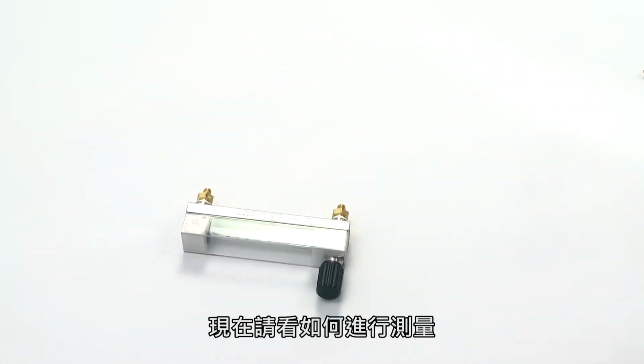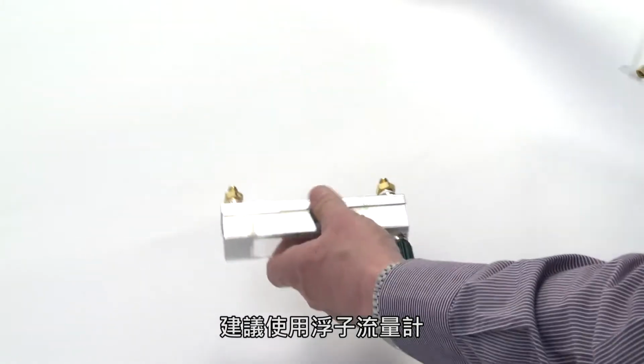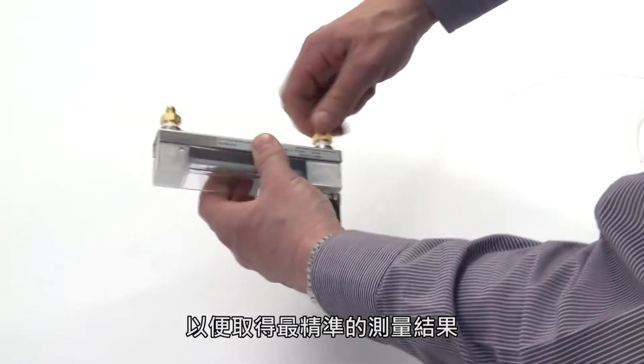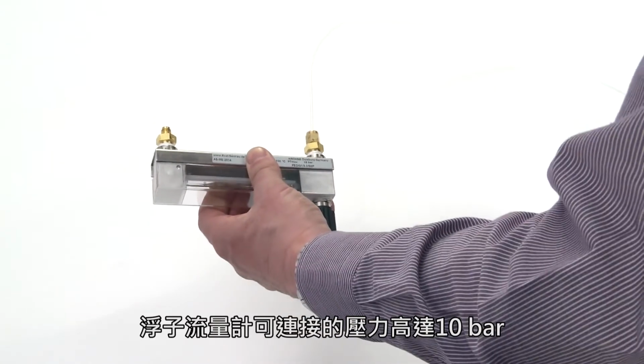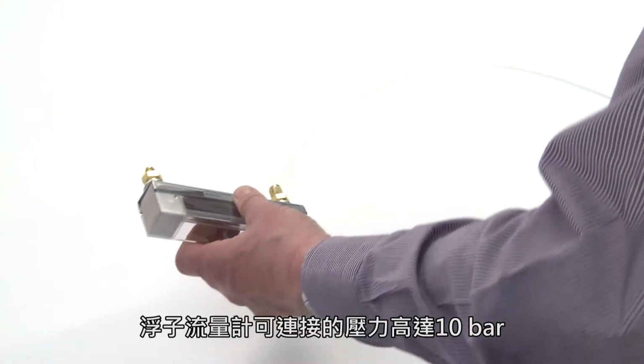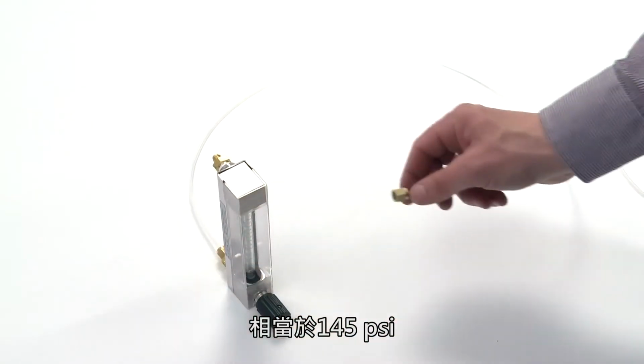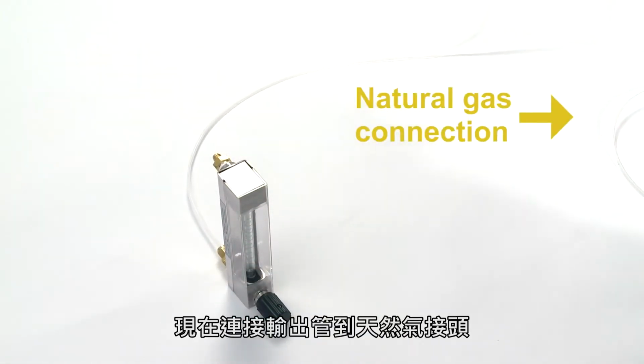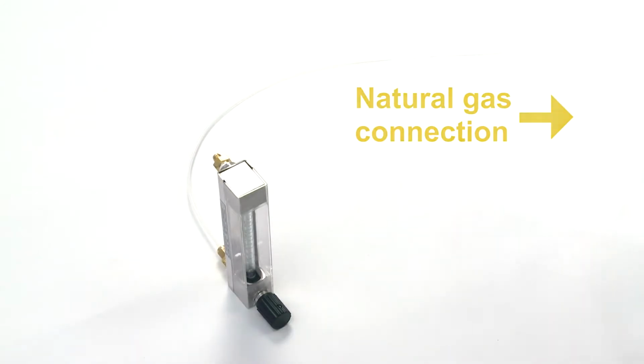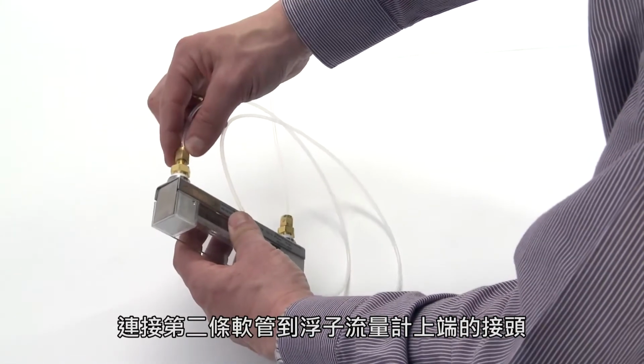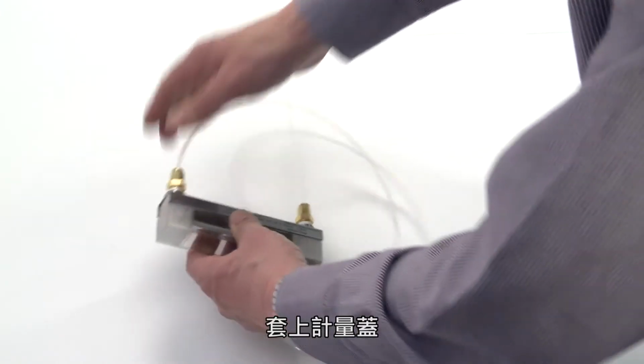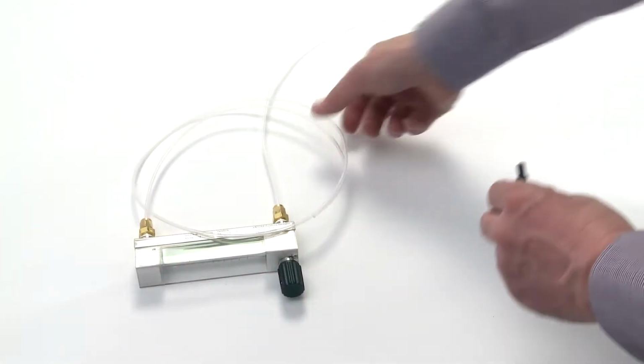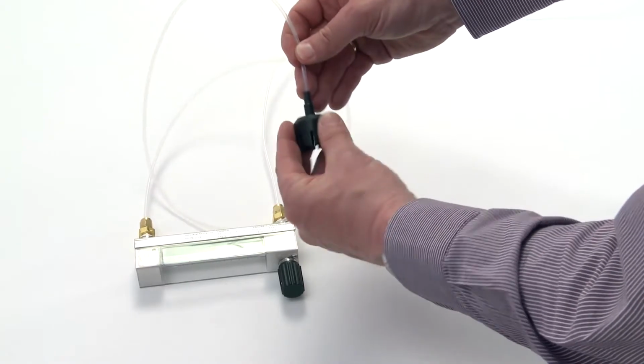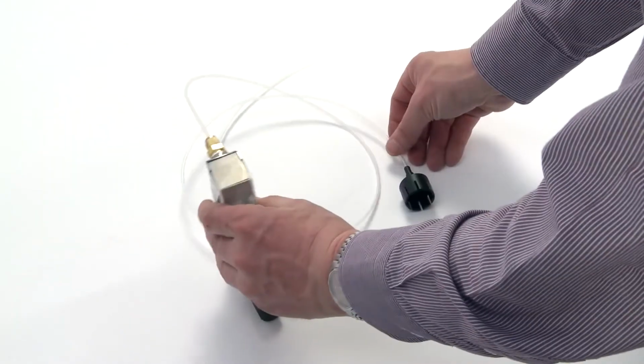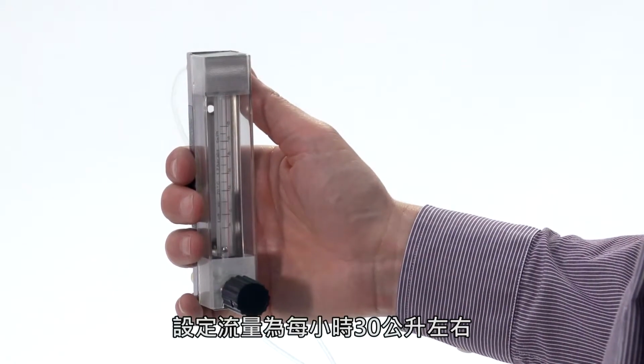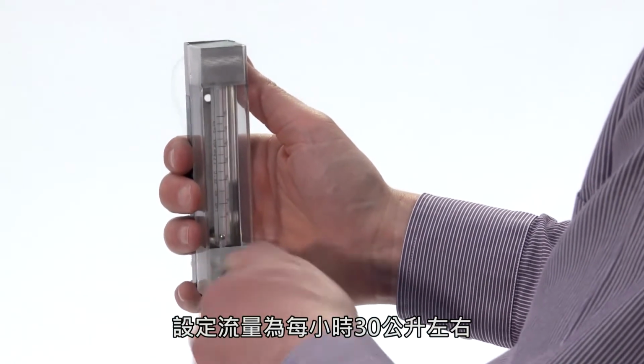Now you see how to perform a measurement. We recommend always using the rotometer in order to get the most precise measurements possible. The rotometer can be used for connection pressures up to 10 bar, respectively 145 psi. Now connect the output line to your natural gas connection. Connect the second tube to the upper connection of the rotometer and attach the measuring cap. Set the flow to approximately 30 liters per hour.